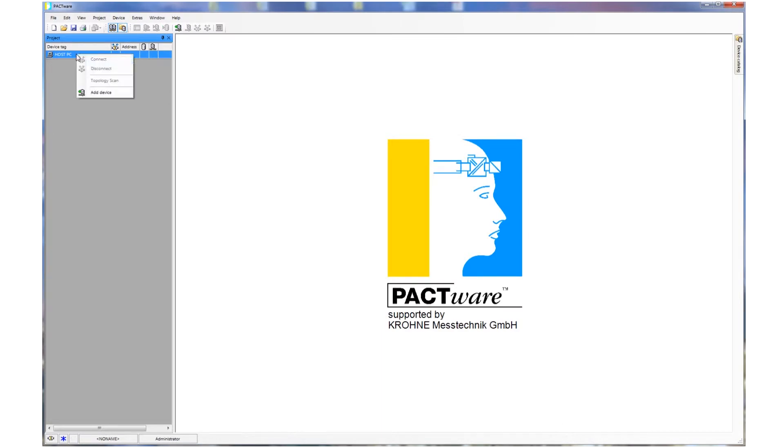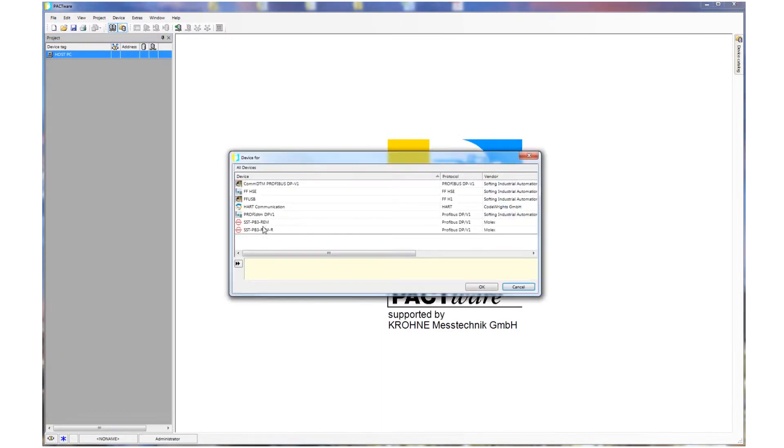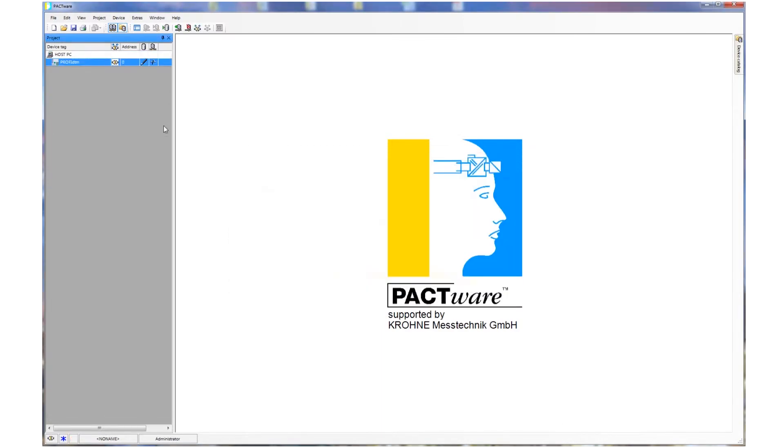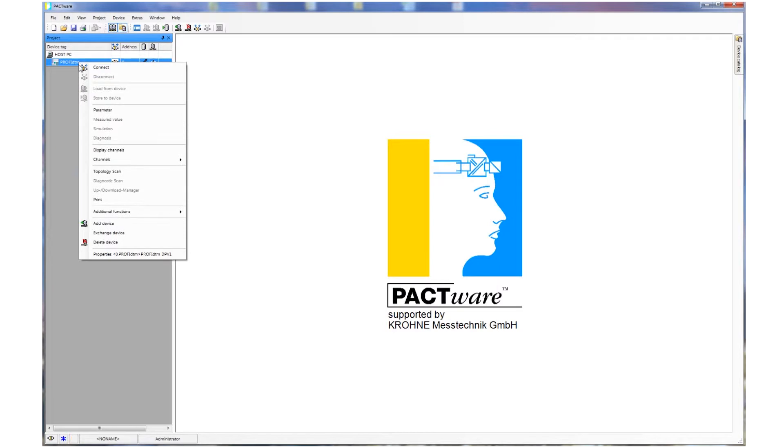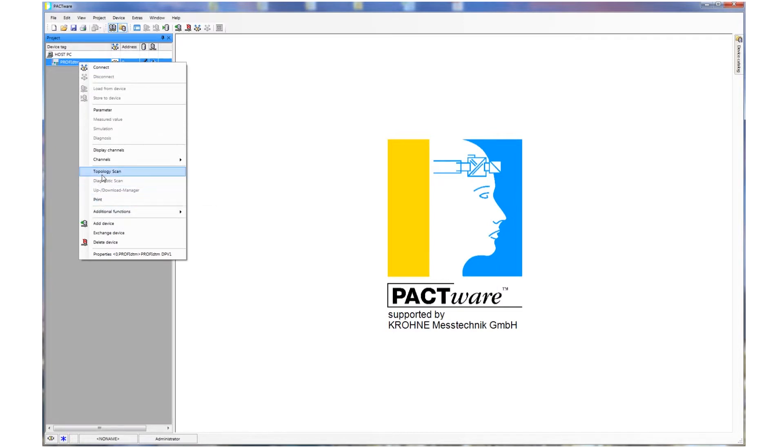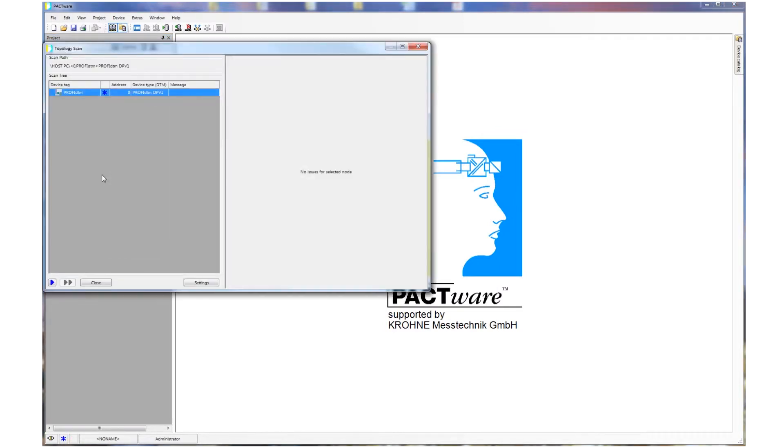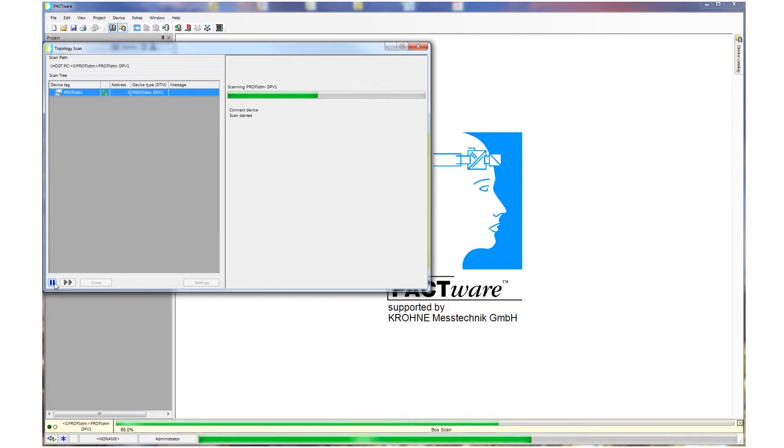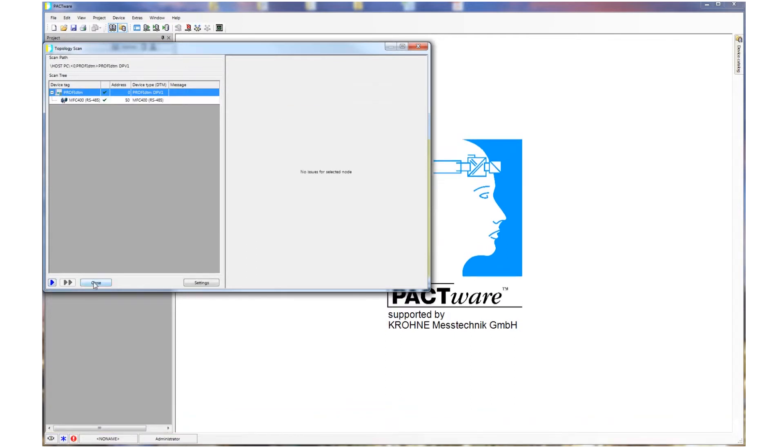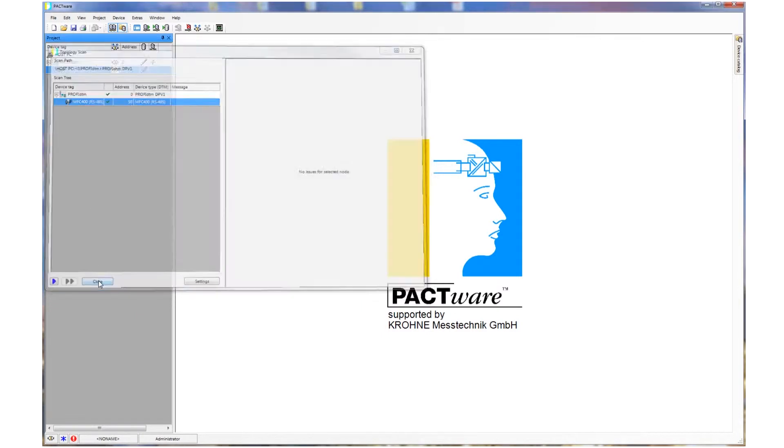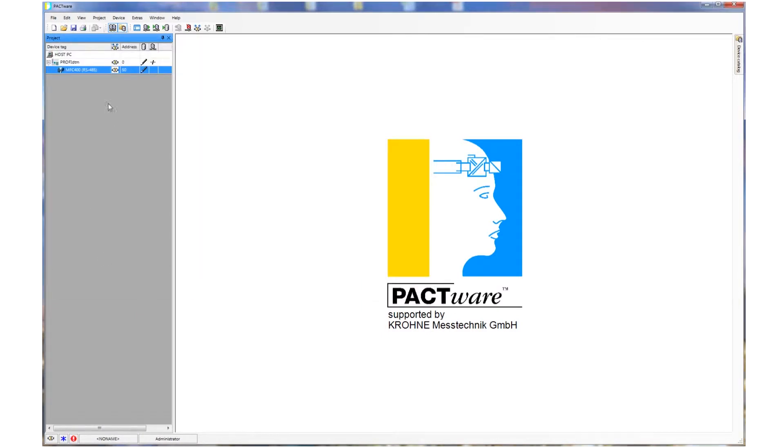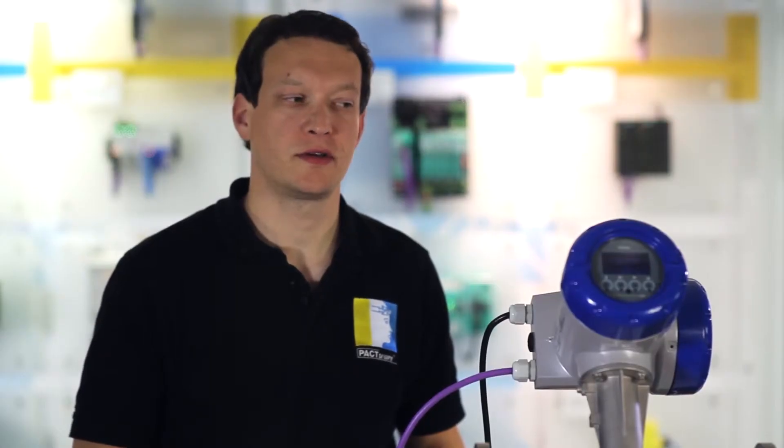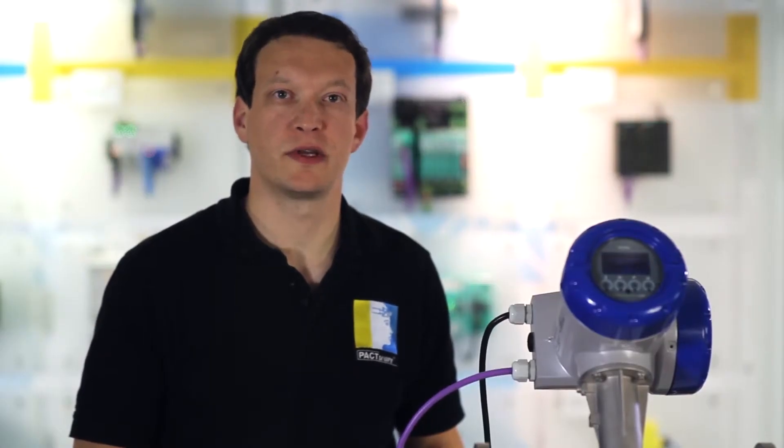After that we could manually add the device DTM to our project. More convenient is using Pactware's topology scan functionality. It scans all bus addresses on each network level and searches for subscribers, and subsequently selects the according DTM automatically.